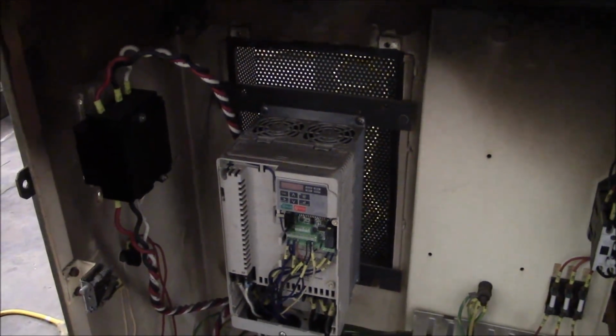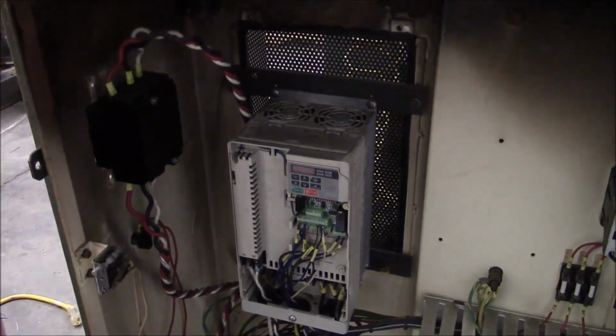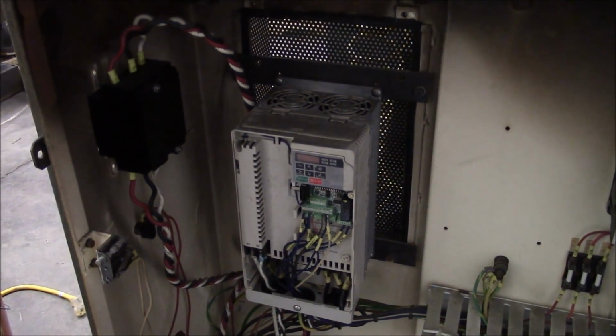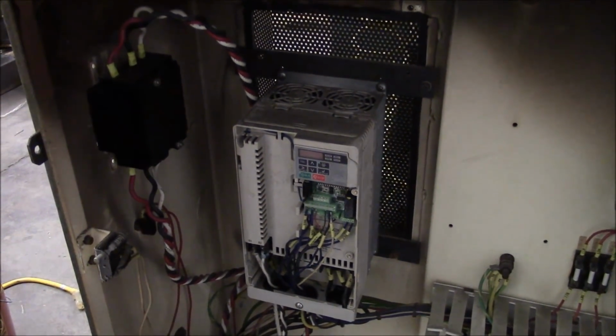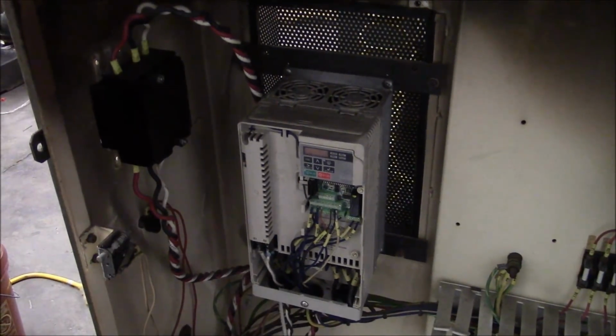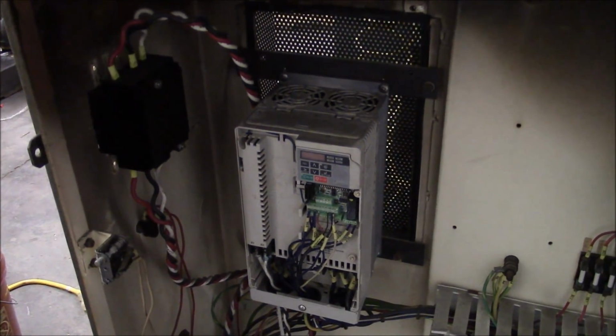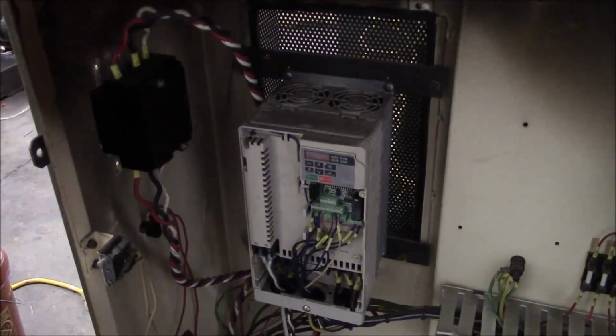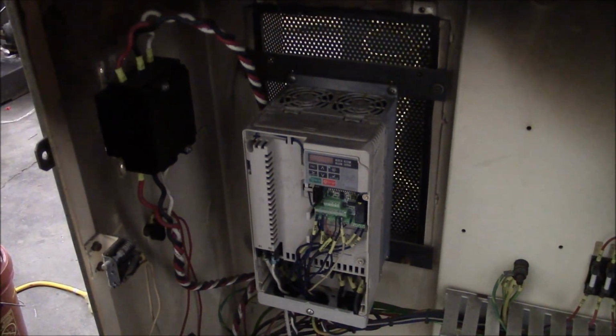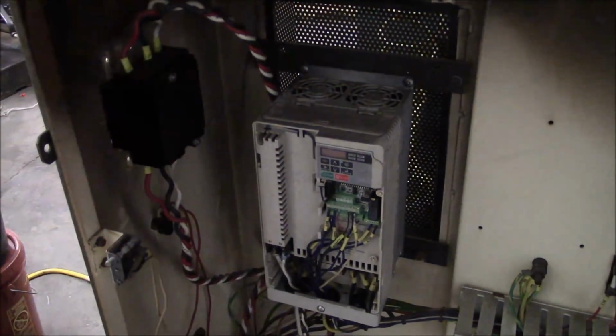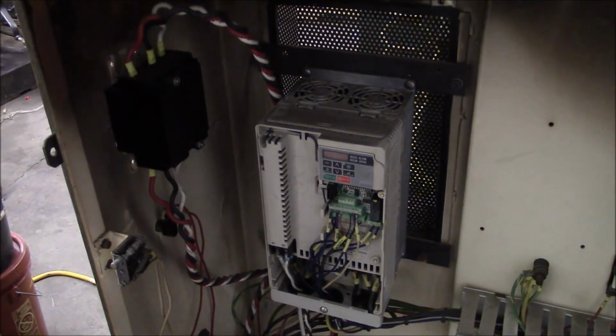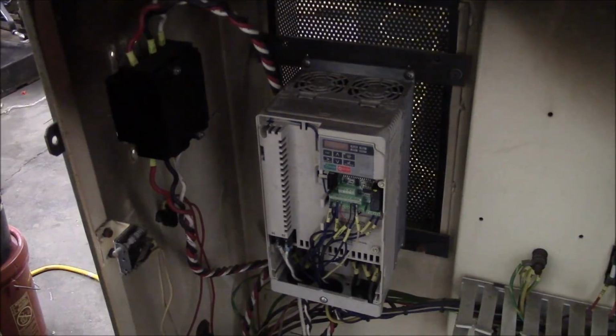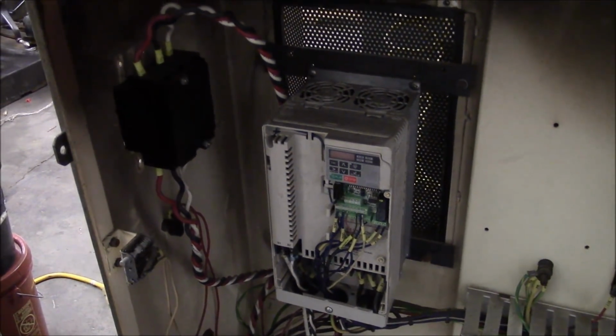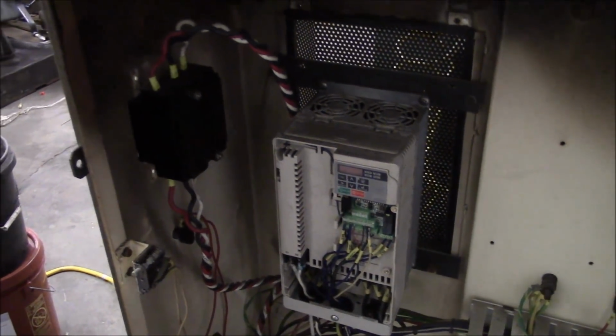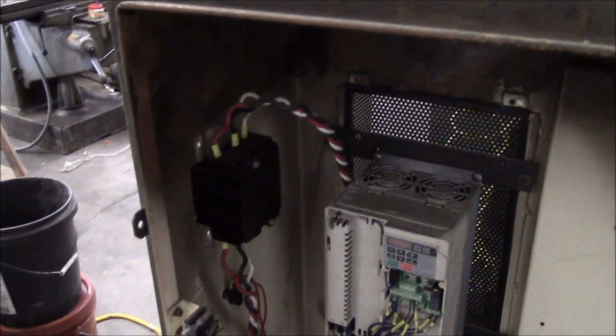And on newer machines, they put a thermistor sensor on those braking resistors, and if they get too hot, it shuts everything down. But these older machines didn't have that, and what would happen is that the module would short, and then the DC bus would just keep feeding that braking resistor, basically turning it into a giant heater. They're rated for so many amps, but they have a duty cycle, and if you exceed that, they'll break down and burn up. So yeah, I'm sure all hell broke loose when that happened.